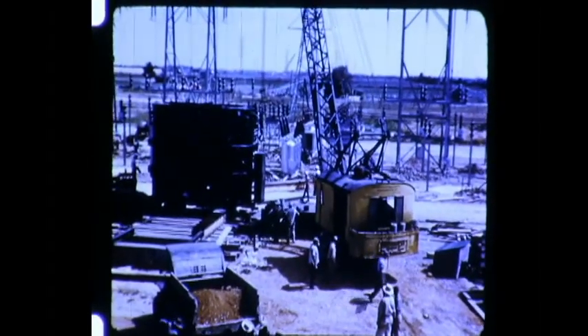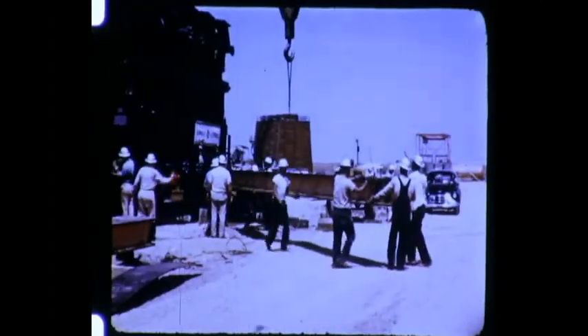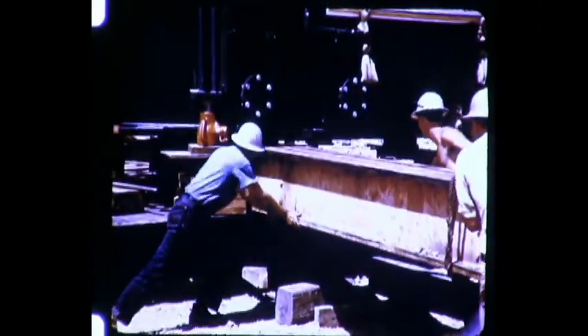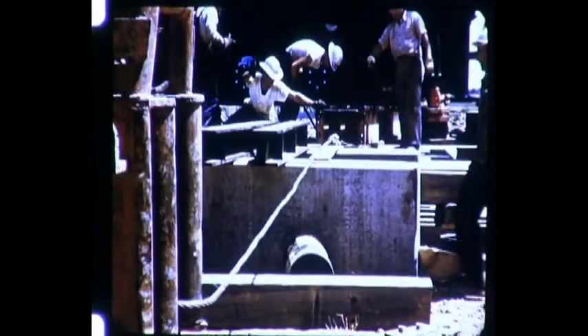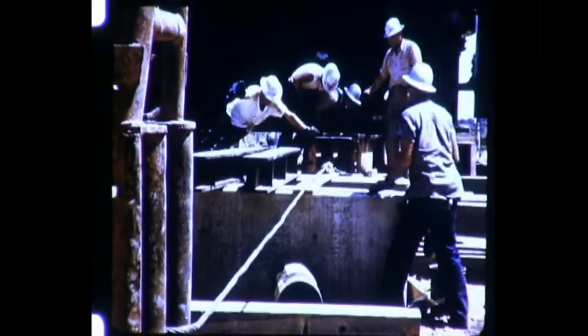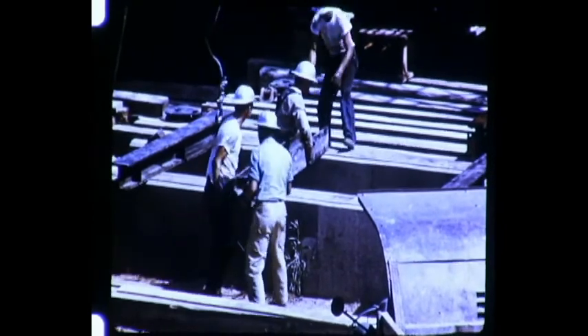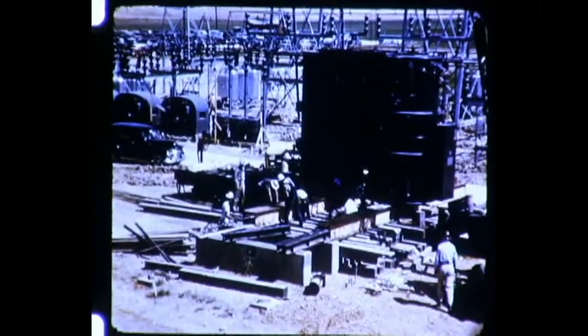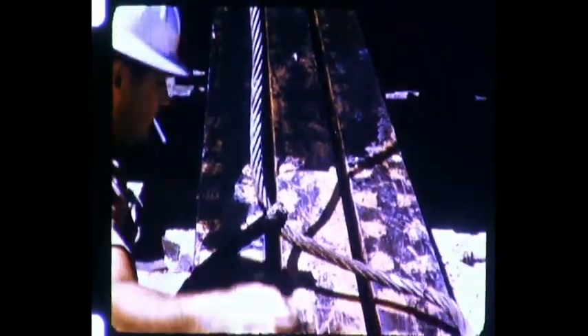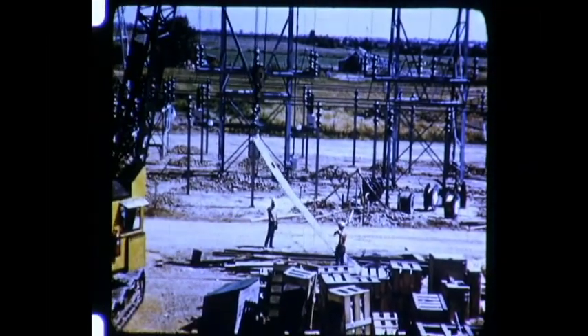With the proper height attained, larger and longer skid beams are brought in. Originally used to set the generators, these beams will support the transformer on the short trip to its permanent position. The large beams are winched through under the unit and across the wooden cribbing area. Meanwhile, the smaller I-beams are positioned on top of the footings. A mixture of grease and graphite is applied to the skid beams so that friction will be reduced during the movement of the transformer. The transformer itself will actually be moved directly on these long, thin skid plates, which will slide like skis over the greased skid beams.